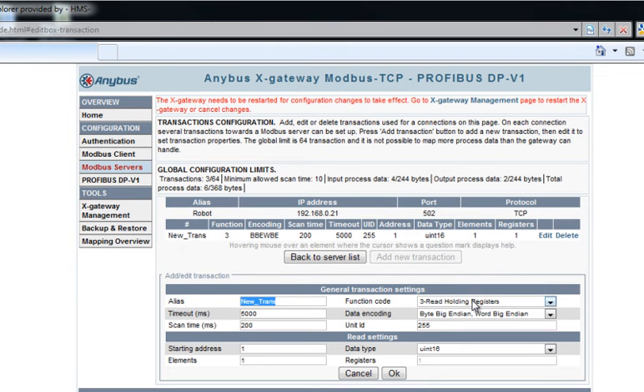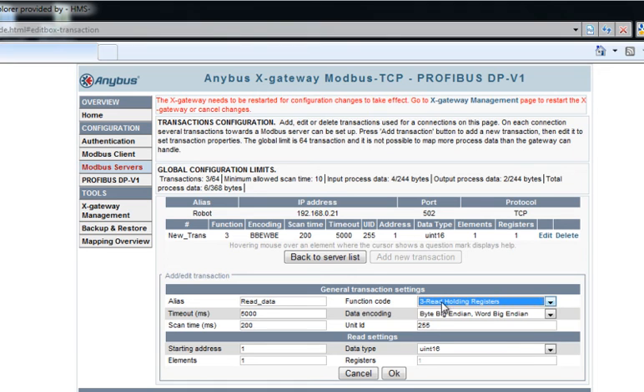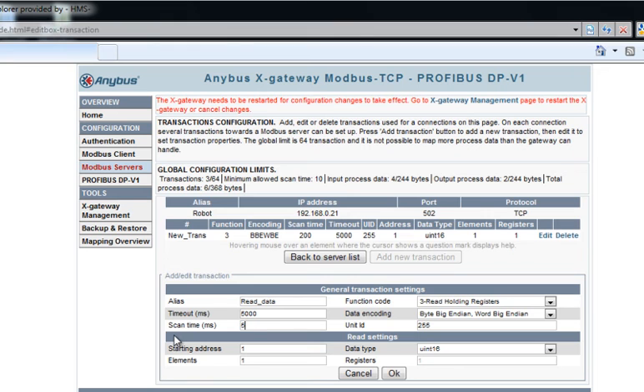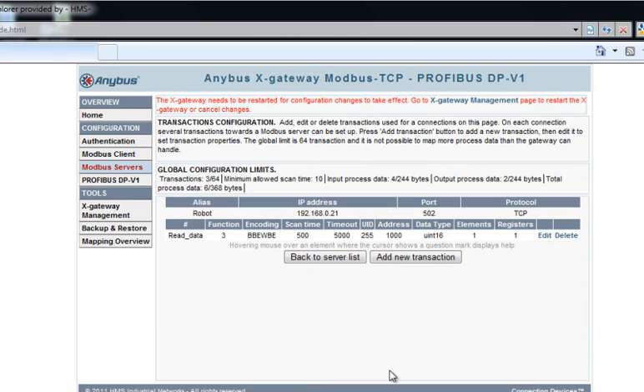Now I need to add transactions to my server to specify what data I want to copy through the gateway. I click Add New Transaction and choose Edit. In this case, I'll set up a transaction called ReadData and specify the Modbus TCP-specific function that I want to use. I can also set up timeout in milliseconds and change the scan time. Scan time specifies the time between repeating transactions. I'll also change the starting address to 1000 and choose the data type I want to use. I click OK to save my settings.